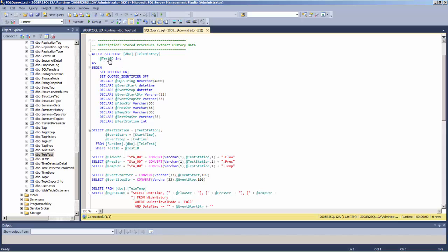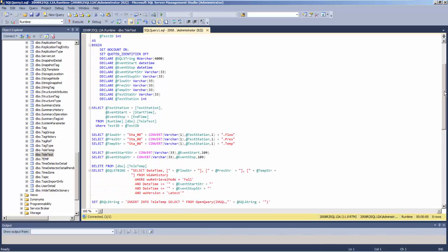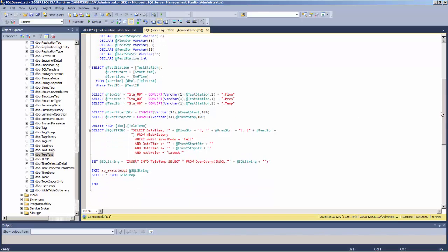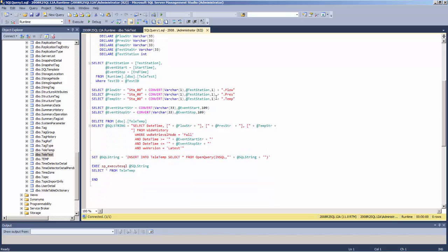This is the stored procedure being called from the SSRS report to extract information from the Wonderware database. We pass in the test ID from the report, which is used to look up the start time and end time of the test. It's also used to populate the process variable tag names we're extracting from the Wonderware database, since we have multiple test stands and need to pick the correct tags depending on which stand we're on. After a datetime conversion, the select statement pulls flow, pressure, and temperature from the wide history table based on those start and end times, then executes the query.